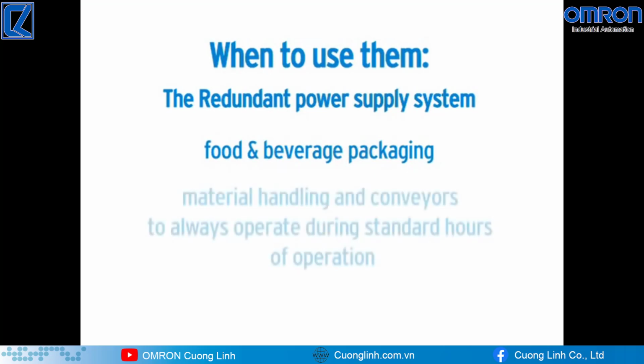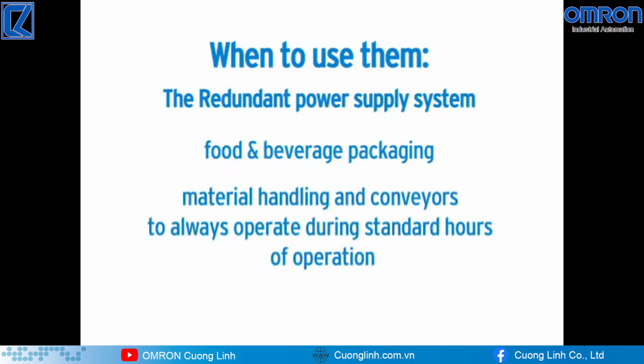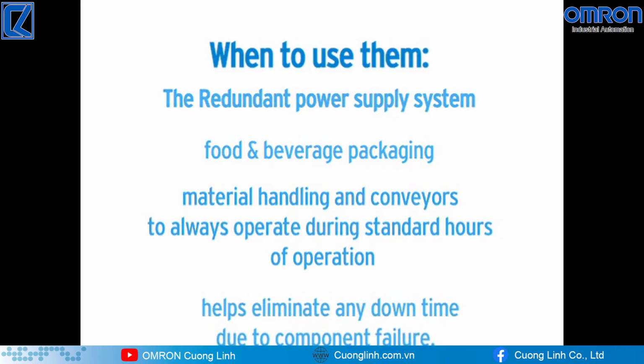The redundant power supply system is a cost-effective way for industrial applications like food and beverage packaging, material handling, and conveyors to always operate during standard hours of operation. In the most automated manufacturing and distribution facility, if the complete plant power goes out, then the operators cannot work. A redundant system helps eliminate any downtime due to component failure.